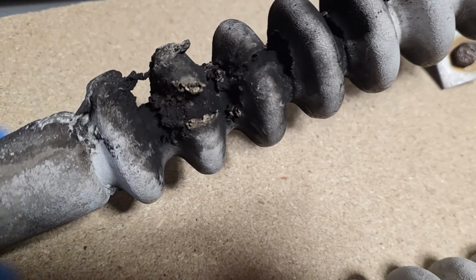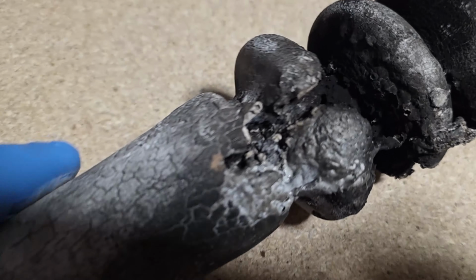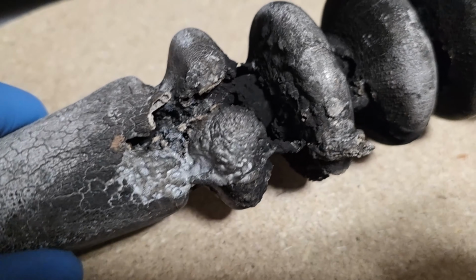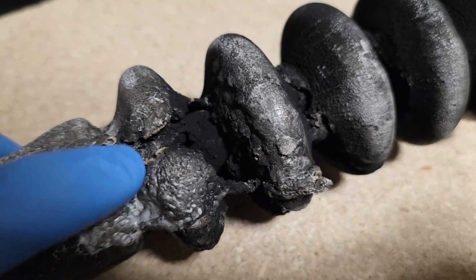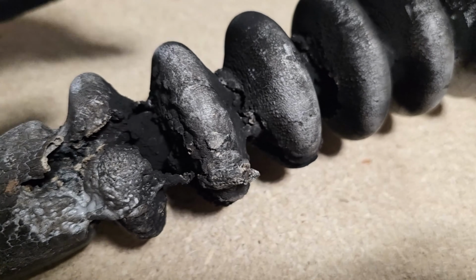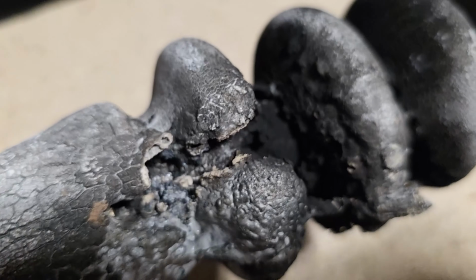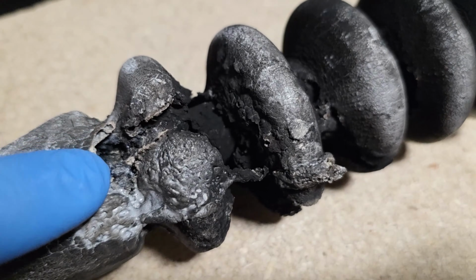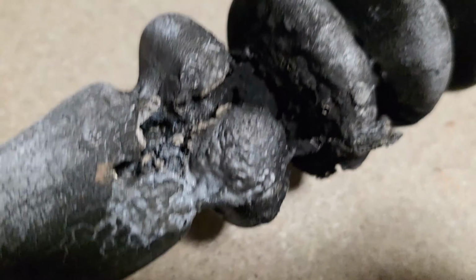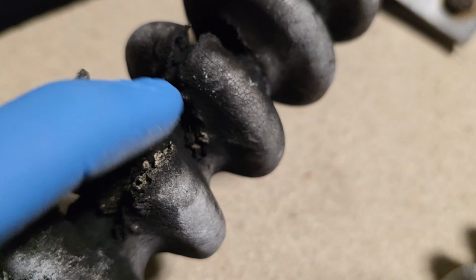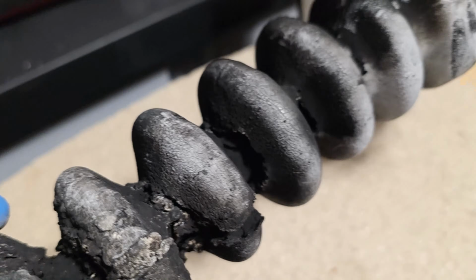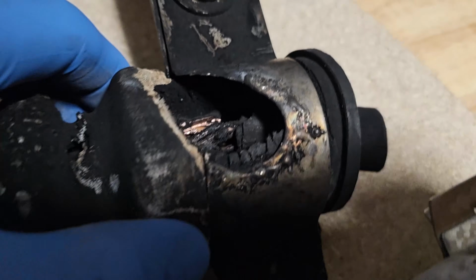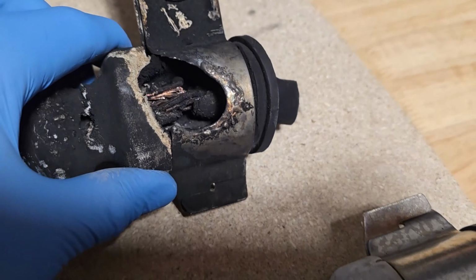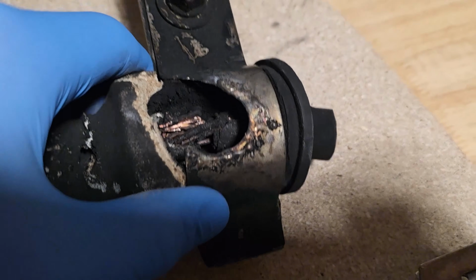But now that we're inside, let's take a closer look at it. So it looks like the failure point - I don't believe it tracked through the epoxy insulator. It looks like it came out and around the surface here. I was going to say it went internal, but it broke right through this particular guy here. It went down through the inside, and ultimately that's where the highest current was as it blew out.